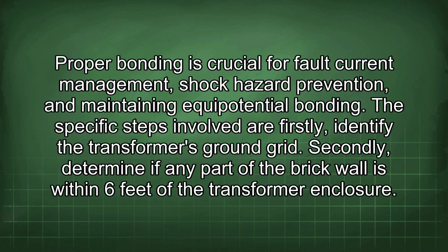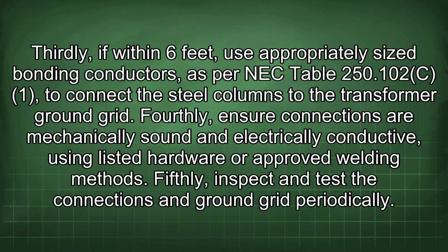The specific steps involved are: firstly, identify the transformer's ground grid. Secondly, determine if any part of the brick wall is within 6 feet of the transformer enclosure. Thirdly, if within 6 feet, use appropriately sized bonding conductors, as per NEC Table 250.102, to connect the steel columns to the transformer ground grid. Fourthly, ensure connections are mechanically sound and electrically conductive, using listed hardware or approved welding methods. Fifthly, inspect and test the connections and ground grid periodically.